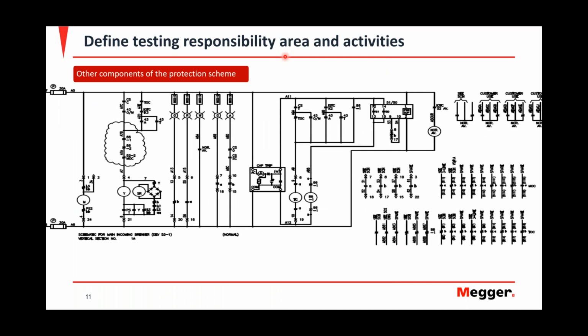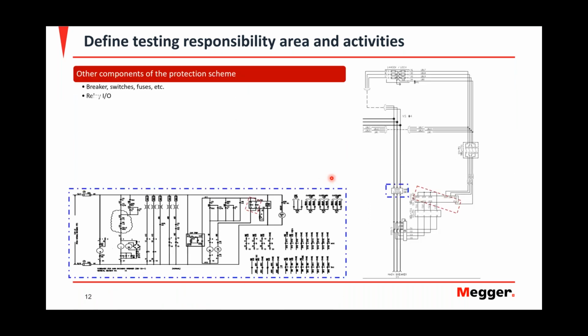This is a schematic for that breaker. This is the DC controller schematic for the breaker. Defining, first of all, you have to be aware that there is not only a relay. When we're doing, let's say, a commissioning test, you have to be aware there are different devices besides the relay. In this case, it could be a breaker, a switch, fuses, all these things that make up your system. So in this case, it would be the breaker. You have to be aware how the relay interacts with the breaker. Know the location of the outputs of that relay as they are electrically located, and how it controls the breaker itself, how it trips it or closes it, whatever the relay is doing.